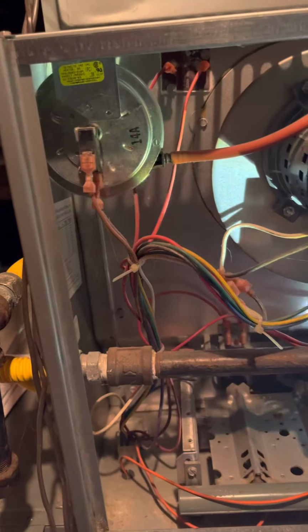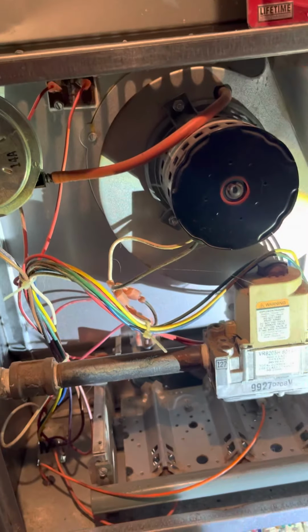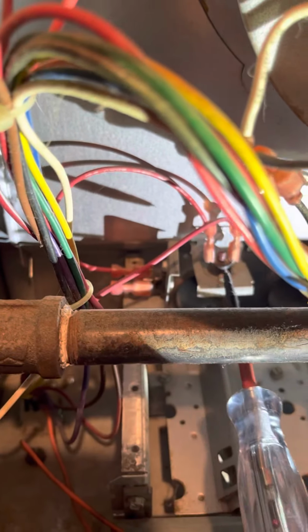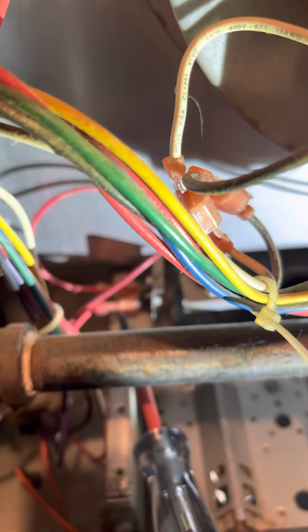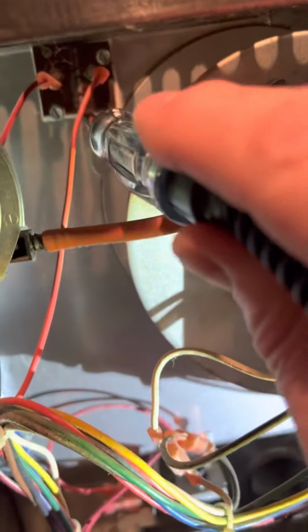Once you energize the circuit and you get 24 volts back on W, then the whole limit circuit will be energized. So you'll have 24 volts coming in, going through the switch, coming back out, coming over to the next rollout, going through the switch, coming back out, going to the next rollout, going through the switch, coming back out, and going through the high limit up here, which you'll have power coming in through the high limit and then back out. So if the furnace is energized and we touch here, and we have a light, we have 24 volts going to this side of the switch, and then we touch this terminal and we don't have a light, then we know that this high limit is open.